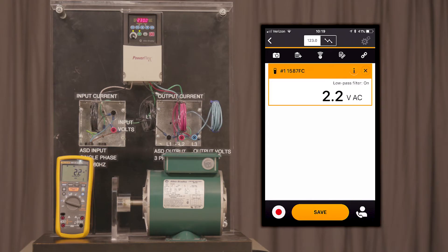Now I'm going to make some current measurements. I'm going to use the I-400 Current Flex. The I-400 Current Flex is a 1 milliamp to 1 amp clamp. What that means is for every 1 milliamp I see on my meter, it represents 1 amp.